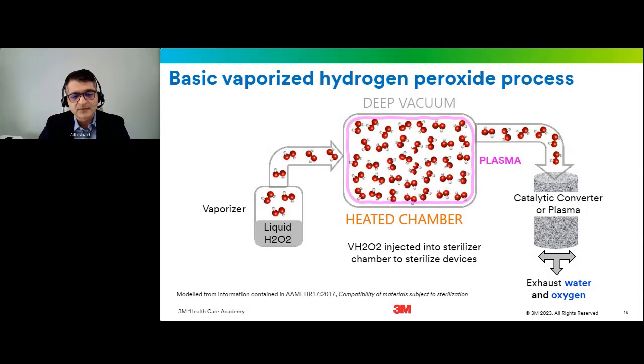What do you call your vaporized hydrogen peroxide sterilizer in your facility? Do you call it a STERRAD, a V-PRO, a gas sterilizer, a VHP, a vaporized hydrogen peroxide system, or a VP4? Based on the different manufacturers and models you have in your facility, or maybe some other general names. I will talk generally about the basis of the hydrogen peroxide processes, because, as the names show, there are differences among manufacturers, but the general concept is the same. The sterilant is in the form of liquid hydrogen peroxide. Liquid hydrogen peroxide gets vaporized, and then the vaporized hydrogen peroxide is injected into the sterilizer chamber to sterilize the devices in the chamber.